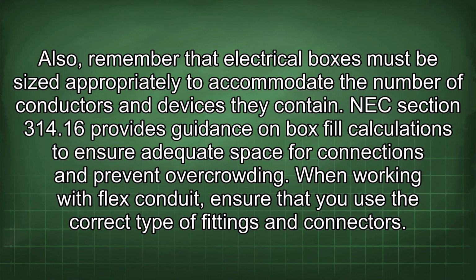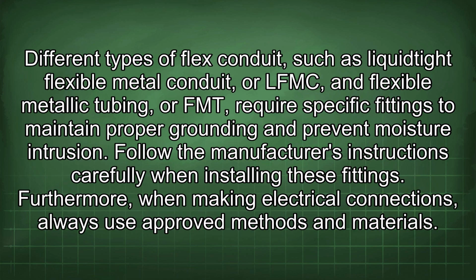When working with flex conduit, ensure that you use the correct type of fittings and connectors. Different types of flex conduit, such as liquidtight flexible metal conduit, or LFMC, and flexible metallic tubing, or FMT, require specific fittings to maintain proper grounding and prevent moisture intrusion. Follow the manufacturer's instructions carefully when installing these fittings.